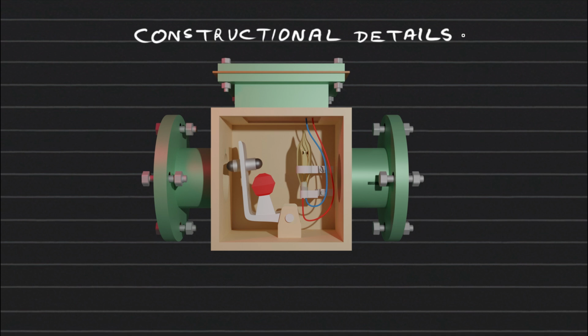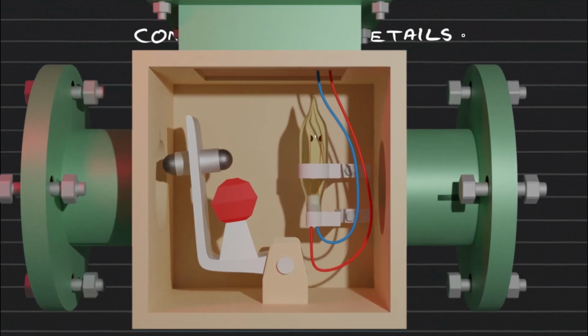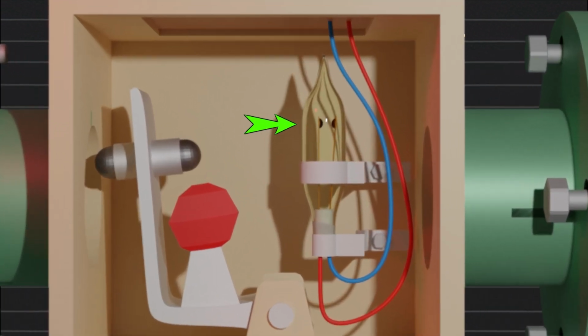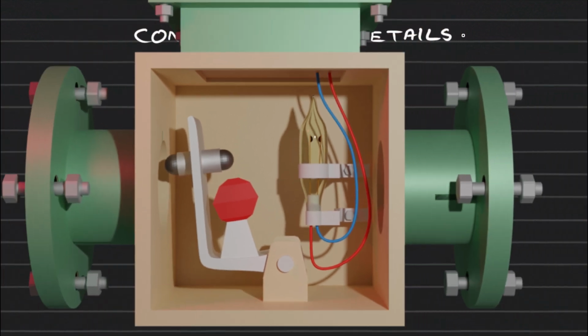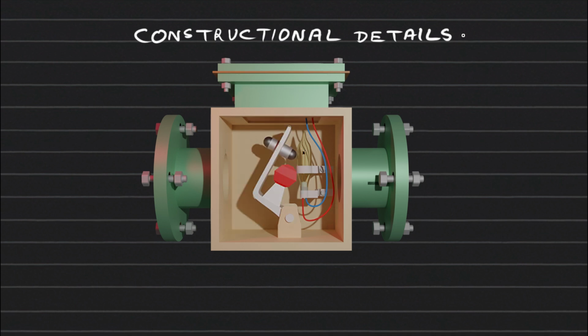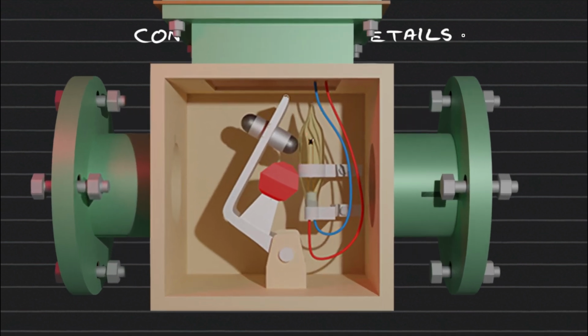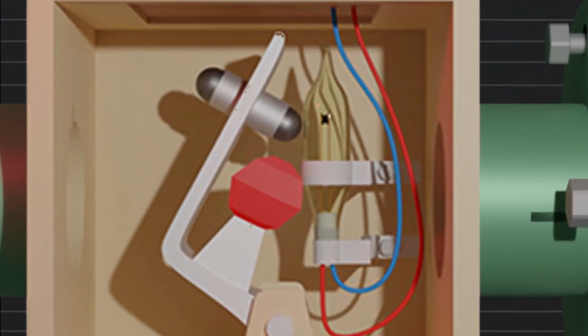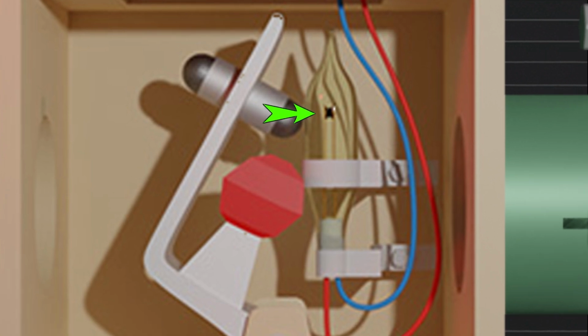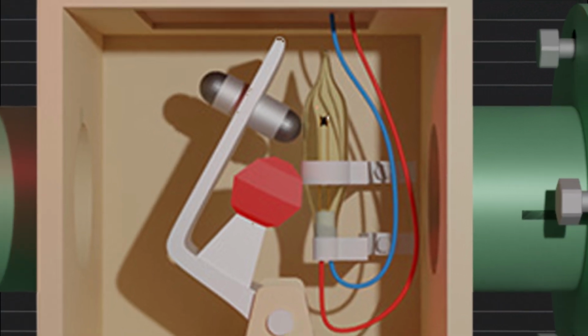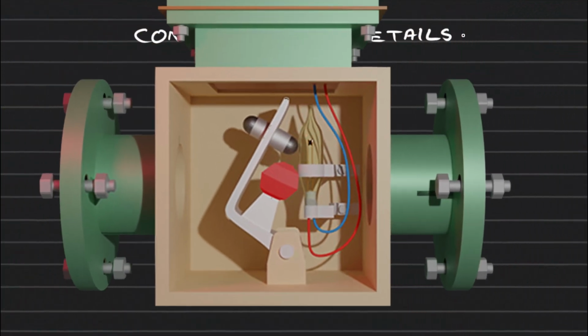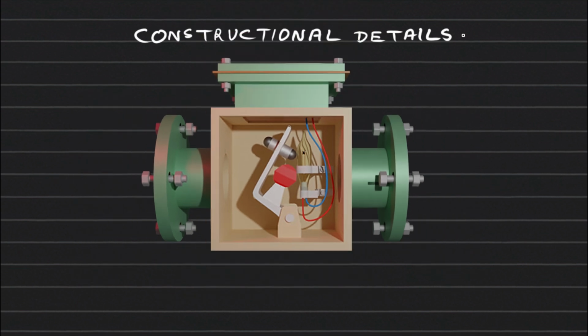The OSR uses a reed switch which has a normally open contact. This reed switch is placed close to the flap magnet inside the chamber. During a heavy fault, the flap rotates and the magnet moves closer to the reed switch. Due to magnetic attraction, the moving contact of the reed switch touches the fixed contact and the circuit gets closed. This closes the tripping circuit of the transformer's circuit breaker, ensuring that the transformer is safely disconnected from the supply.